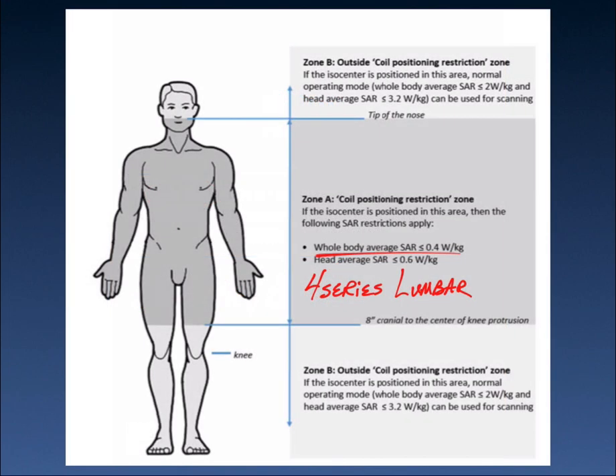We're going to follow the whole body conditions for a 1.5 Tesla system. In the conditions of use for the NEVRO spinal cord stimulation SENZA system, the SAR values depend on what area of the body over which you will center or landmark. We're going to use Zone A. In this particular zone, if the isocenter is positioned in this area, then we're going to limit the whole body average SAR to 0.4 watts per kilogram.